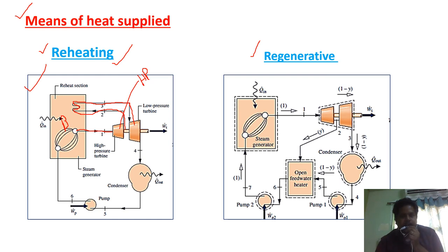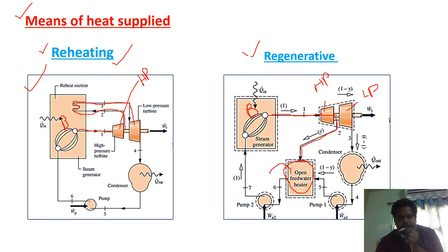This is what happens in reheating, and this type of turbine is called a reheating turbine. The next type is the regenerative turbine. From the boiler, steam enters the high-pressure turbine. After expansion through the high-pressure turbine, before entering the low-pressure turbine, some amount of steam is extracted and sent to an open feed water heater, which preheats the water before entering the boiler, reducing the energy required to convert water into steam.